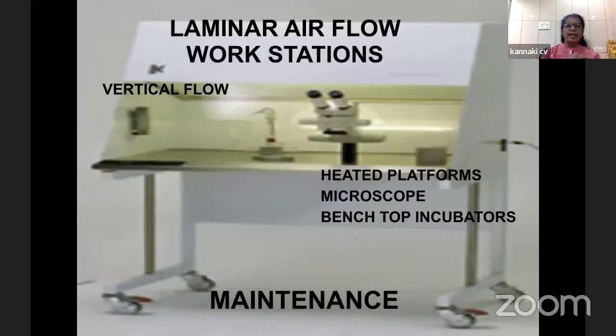Then the laminar flow workstations are very customized now. We have heated stages in microscopes incorporated. You can have the benchtop incubators, the MINC incubators there, and the positive flow is also metered. There are meters to check the flow. It's a vertical flow, so it's very customized and good. But you have to keep checking the particle count on this.